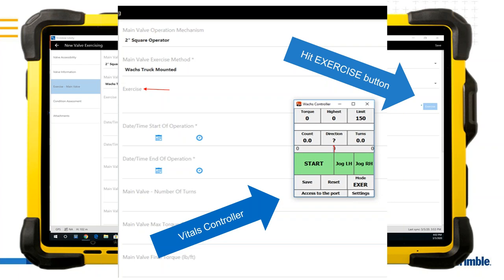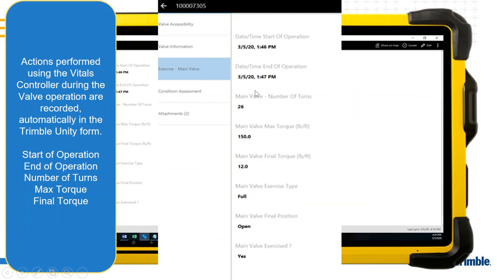Once the valve has been fully exercised, you close the Wachs controller and it automatically populates all the characteristics and data stored on the valve operating machine into the Trimble Unity form. This auto-populated data includes the start and end of the operation — giving a precise reading of how long it took to operate the valve — which can feed into work management systems for tracking time and materials.